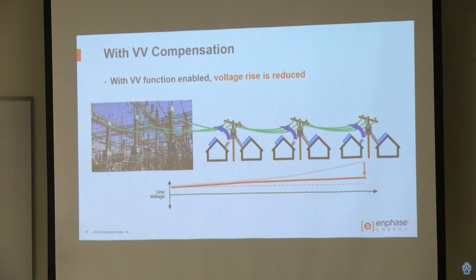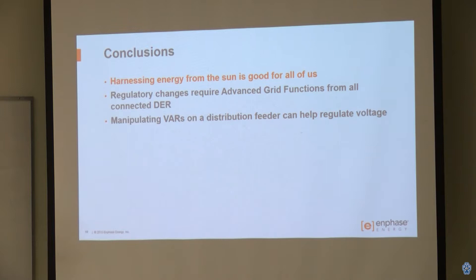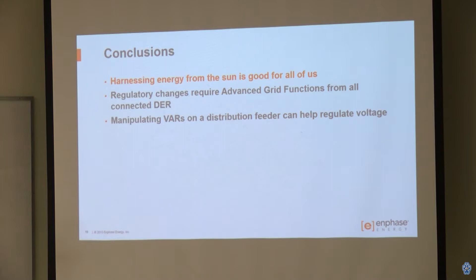So in conclusion: harnessing energy from the sun is good for all of us — I highly recommend going into the solar field. I've been in multiple electronic disciplines and this is the most rewarding. Regulatory changes — California Rule 21, Hawaii Rule 14H, IEEE 1547 — all require advanced grid functions for all connected DER. When we manipulate the VARs at the distributed energy resource where we're generating, we can affect the voltage on the distribution feeder.